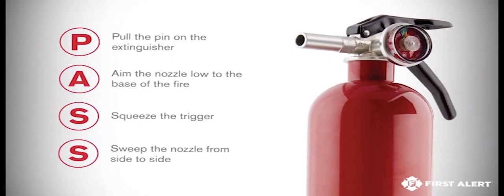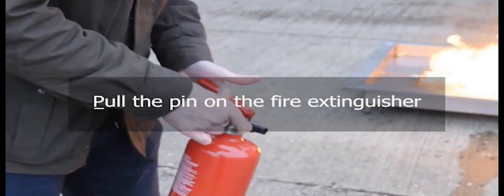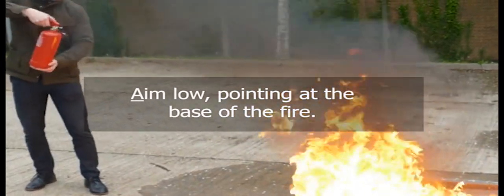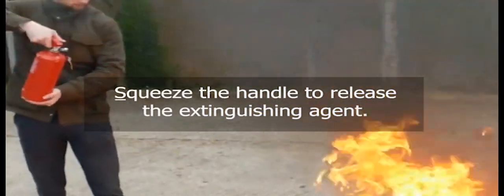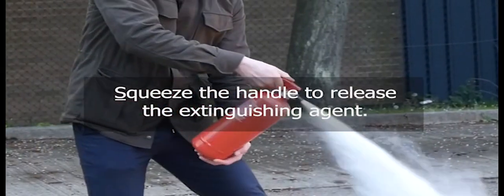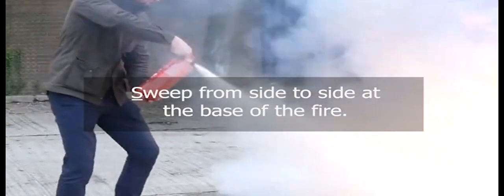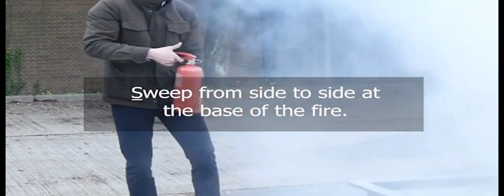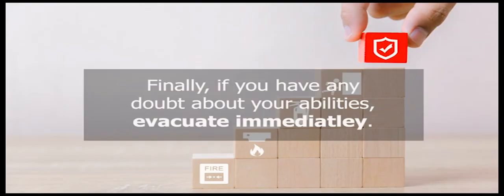Most extinguishers operate using the following PASS technique. Pull, you pull the pin. Aim low, pointing the extinguisher nozzle at the base of the fire. Squeeze the handle to release the extinguishing agent, and sweep from side to side at the base of the fire. Watch the area and be prepared if it reignites. Once again, if you have any doubt about your abilities to fight a fire, evacuate immediately.